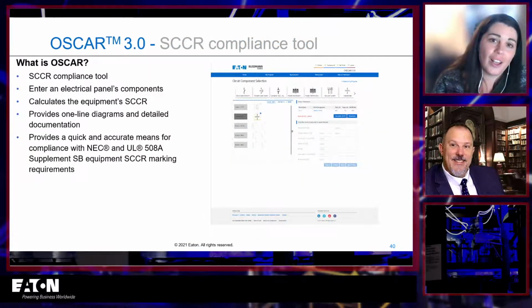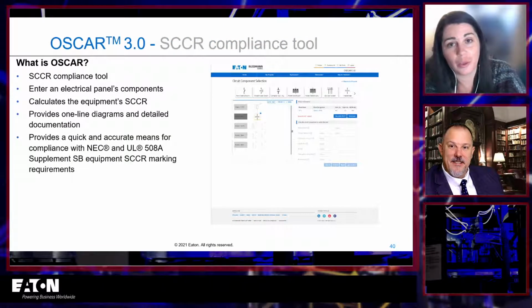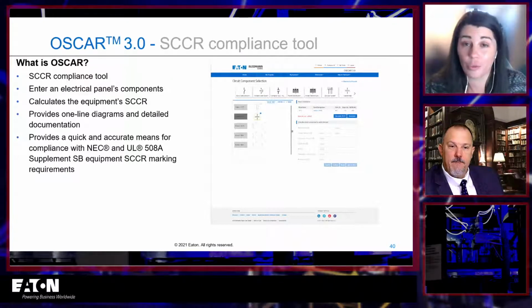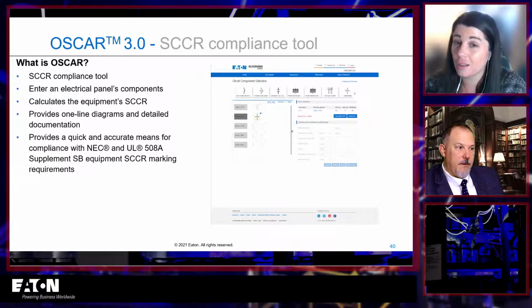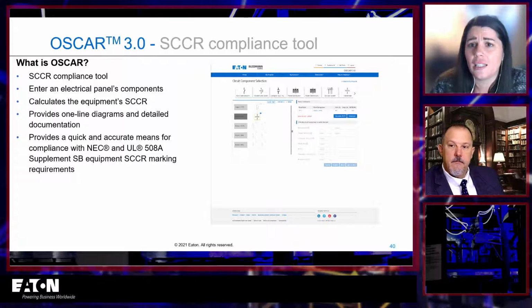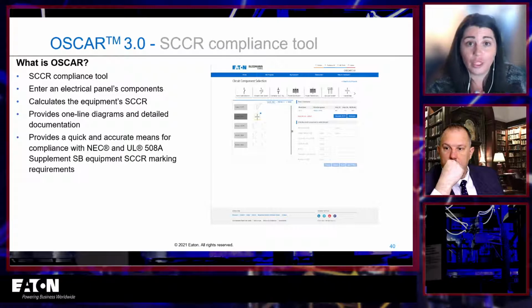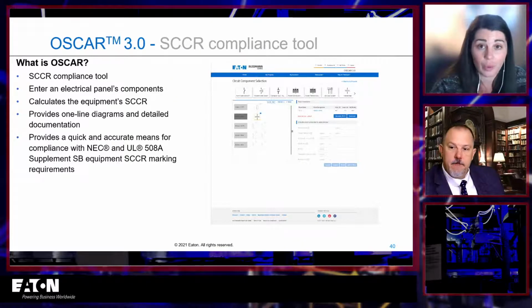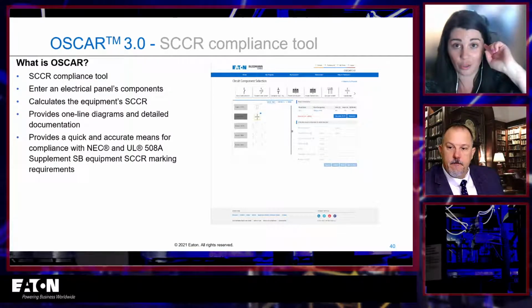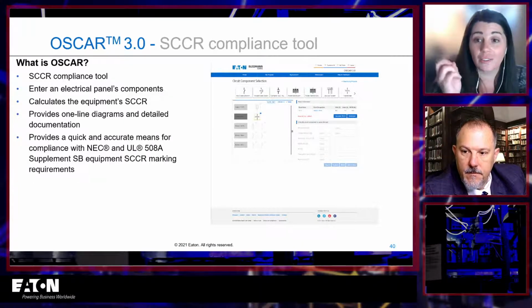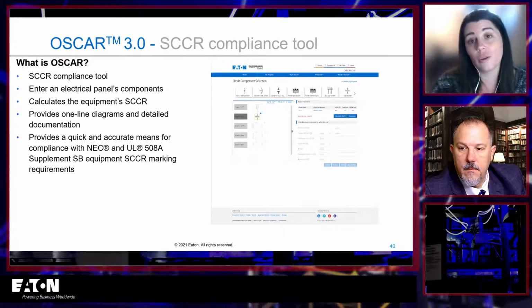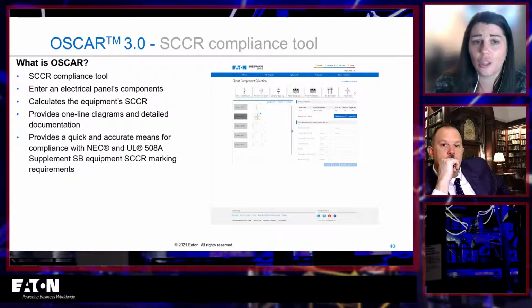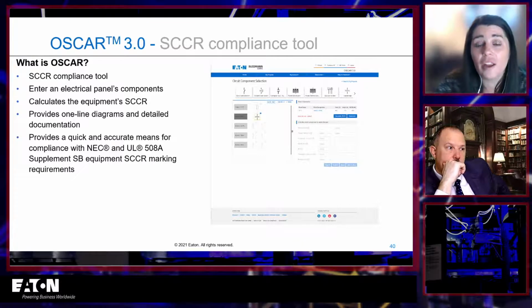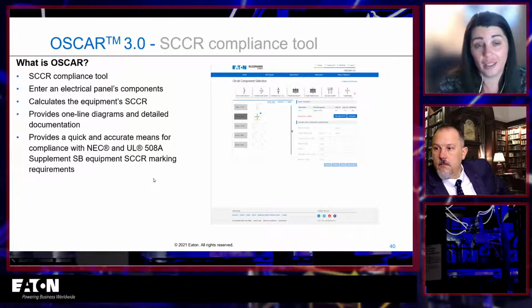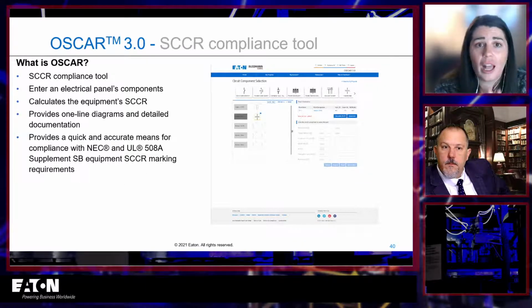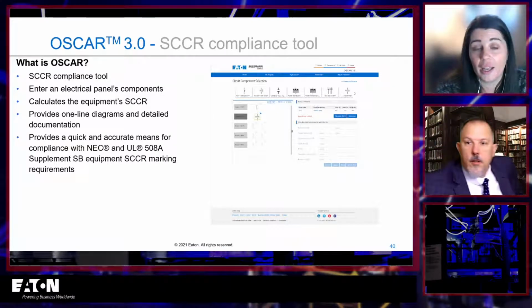So now, one more thing: Oscar 3.0. This is a really cool tool that Bussmann has come out with. Oscar has been around for a while, but Oscar 3.0 is brand new this year. I think it's maybe a month old since it launched, maybe not even. Oscar 3.0 is an SCCR compliance tool. You enter your electrical panel components, and you actually get to drag and drop. It's so much more user friendly than Oscar 2.1 because you drag and drop these components and define them. You get to say, I'm using an Eaton contactor, or I'm using a Square D breaker. You specify the exact one that you put in there. Then it provides a one-line diagram and detailed documentation and calculates the short circuit current rating. It's a quick, accurate means to use UL 508A Supplement SB to determine your SCCR.